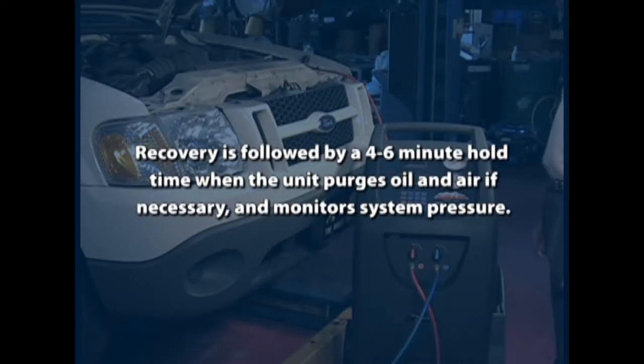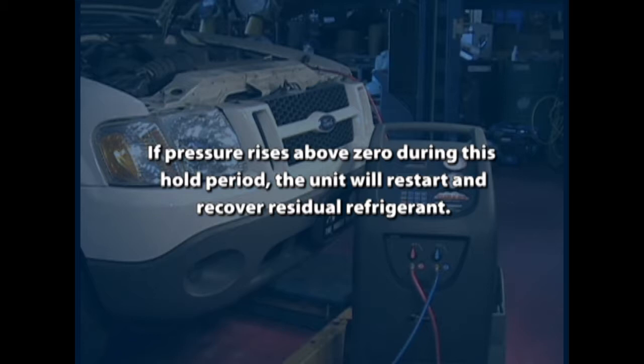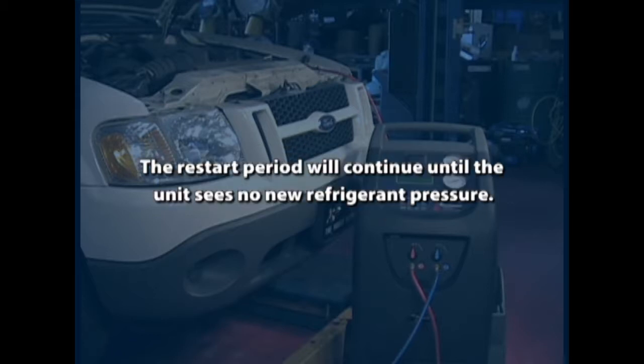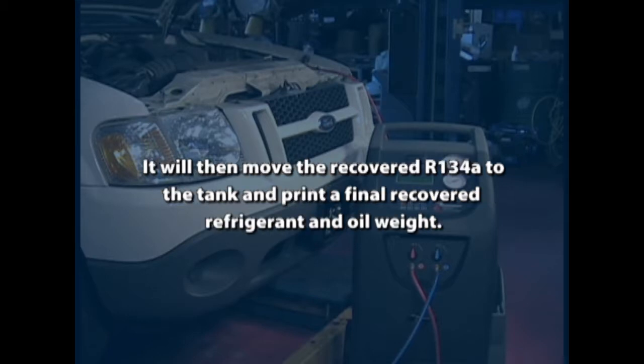Recovery is followed by a 4 to 6 minute hold time when the unit purges oil and air if necessary and monitors system pressure. If pressure rises above 0 during this hold period, the unit will restart and recover residual refrigerant. The restart period will continue until the unit sees no new refrigerant pressure. It will then move the recovered R134A to the tank and print a final recovered refrigerant and oil weight.